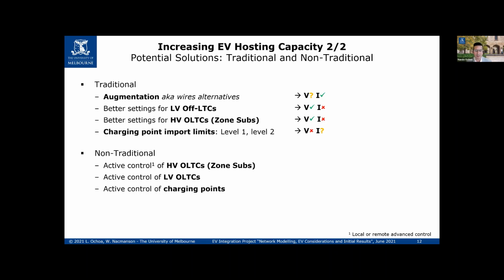You need a sophisticated way of estimating what import limit will not affect your voltage drops. Same thing with the non-traditional options: controlling in a very active way the voltages of on-load tap changers in the primary subs, the zone subs, or the distribution transformer means we are actually doing something in terms of the thermal aspects of our conductors and transformers.